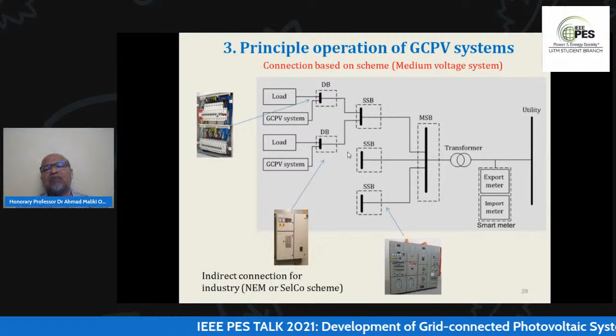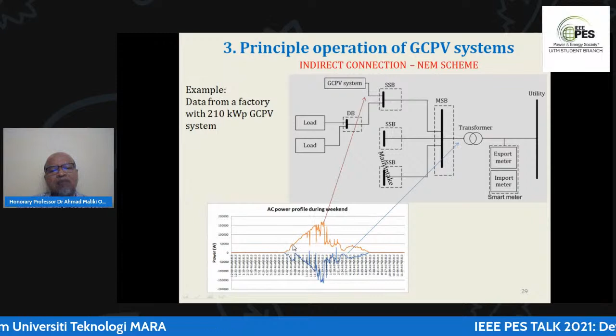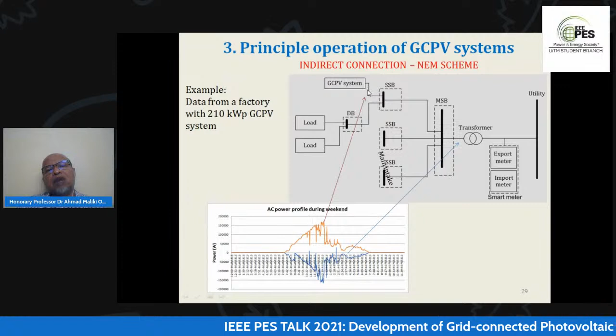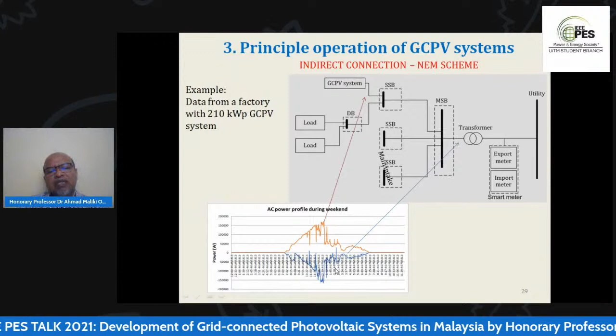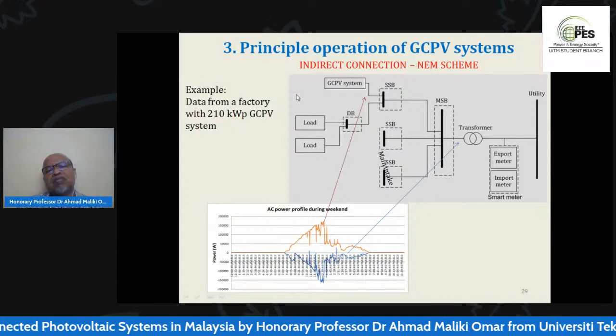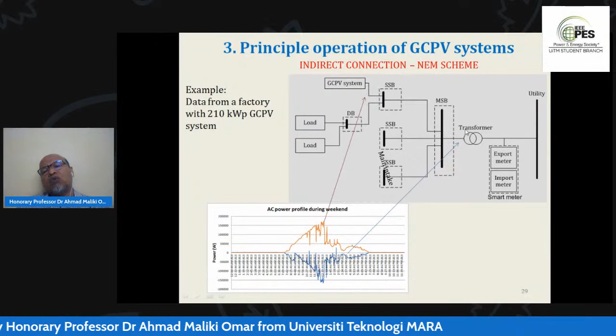This is an example where we put the data logger here, a power analyzer, connected to the GCPV system at this point, and also at this point. This is what happened during the weekend, Saturday and Sunday. If you look here, this is a positive value — that means power coming out from the GCPV system. Here we tag a negative power, which means because the load during weekend has a lot of shutdowns, not many activities, most of the power generated here goes to the grid, recorded by the negative value.